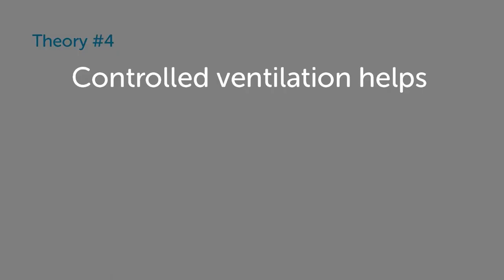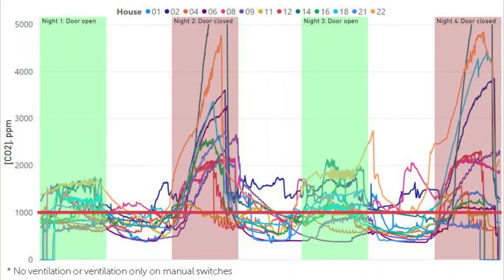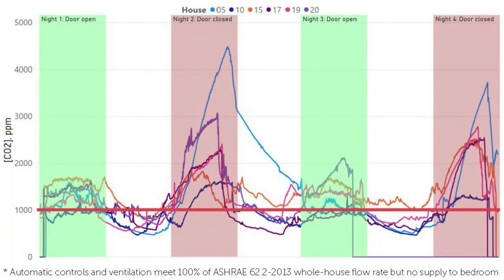Theory number 4: intentional ventilation helps. This graph shows the 13 homes with no ventilation or ventilation controlled using a manual on-off switch. This graph shows homes with ventilation systems that have fully compliant controls to meet 100% of ASHRAE ventilation levels, or a balanced ventilation system. Note that none of these systems have direct supply to the bedroom. These systems do not perform well at all.